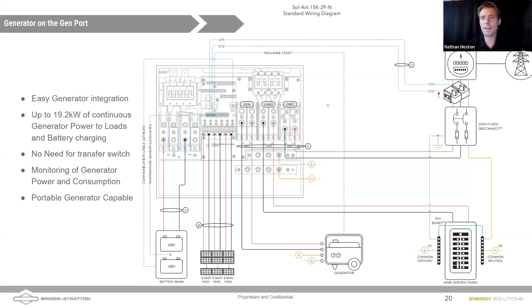So here's another example of integrating a generator. I guess we don't show the generator here. Oh, we are showing the generator. Sorry, the picture. Yeah, so this is an example of us bringing a larger generator. When we use the grid port, we can have a larger generator than we could otherwise leverage on the gen port on the Sol-Ark. What's the limit here, Daniel, with using a transfer switch? What's the difference between bringing the generator in on the gen port and bringing it in through a transfer switch? It's 19,200 watts, I believe, on the gen port, whereas this, we can really bump it up to, I think, 200. Well, if it's 200 amps, that'd be 45.